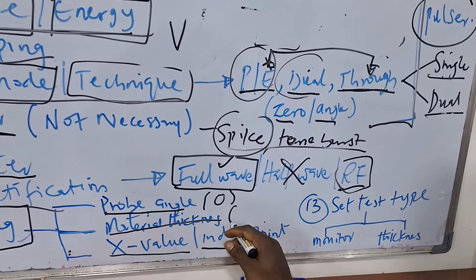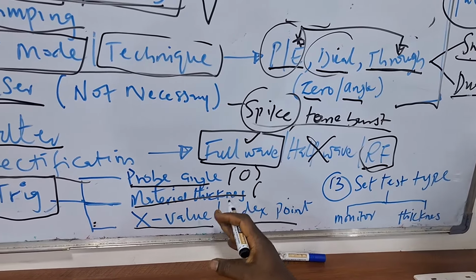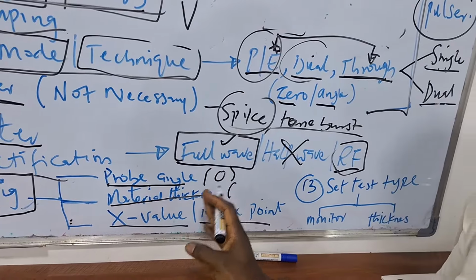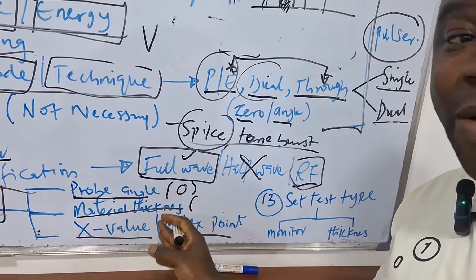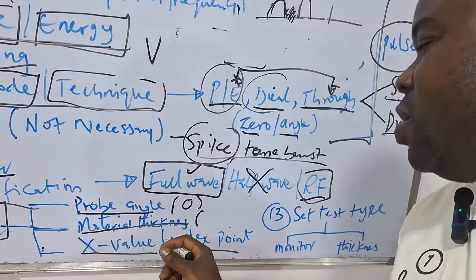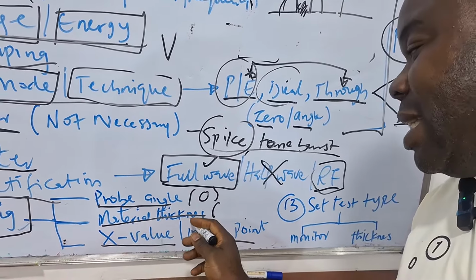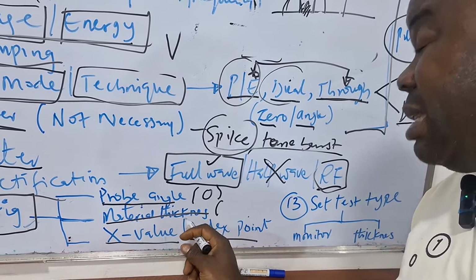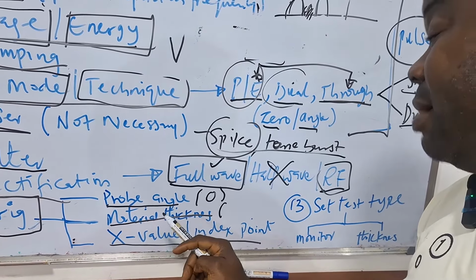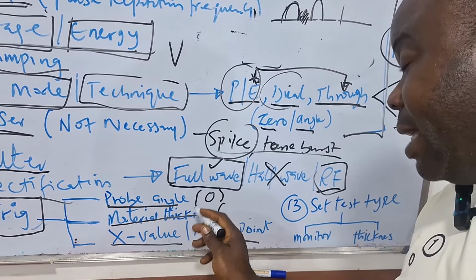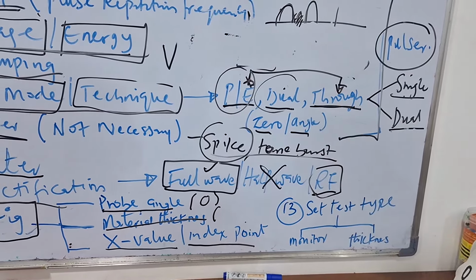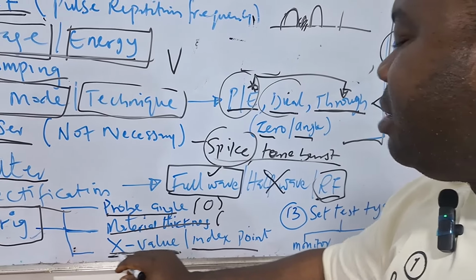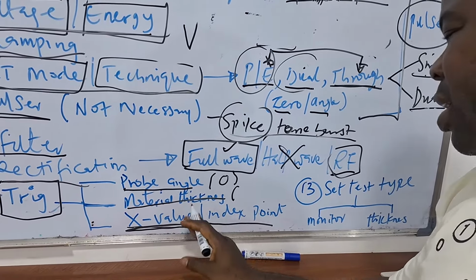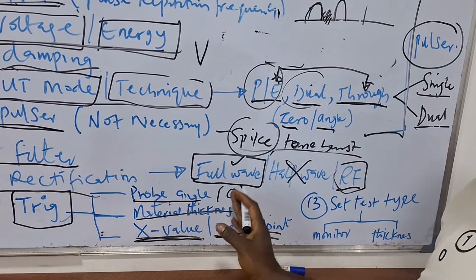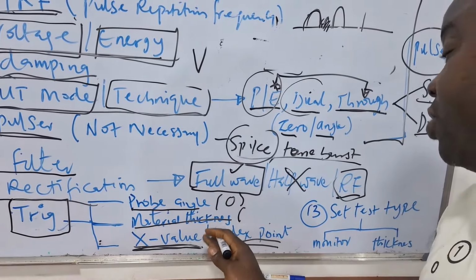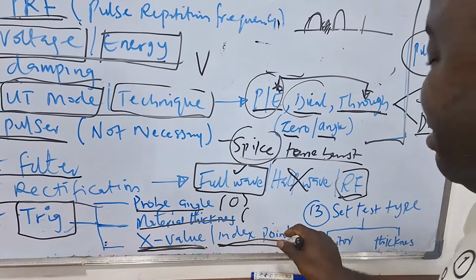Your material thickness may not be consequential when doing your 0 degree setup and calibration, but in shear wave, when you start weld inspection, you must input the right material thickness. Otherwise, you'll get wrong thickness or depth readings when you see an indication. For your 0 degree setup, your X value, the index point, will be 0, since it doesn't really apply here.